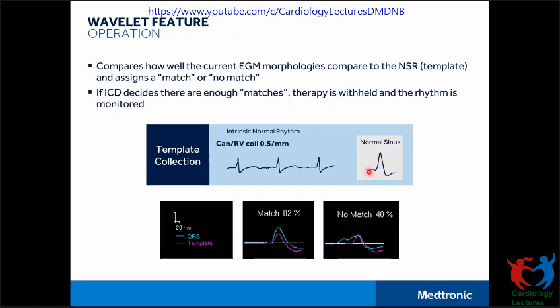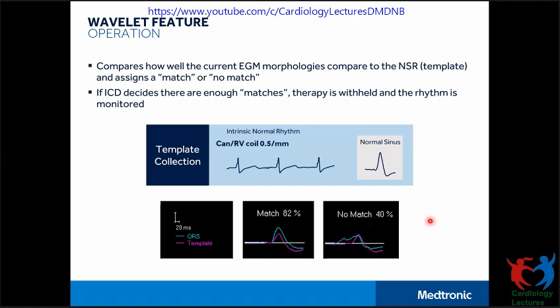Wavelet actually collects a template during sinus rhythm and then compares the stored template with the current EGM morphology. It assigns a match score as a percentage and calls a complex a match if this match score is equal to or more than 70, as seen in this image. On the right side it says 'no match' with 40 percent, meaning it is below the match threshold which is normally set at 70. On this basis it determines whether it's an SVT or a VT.